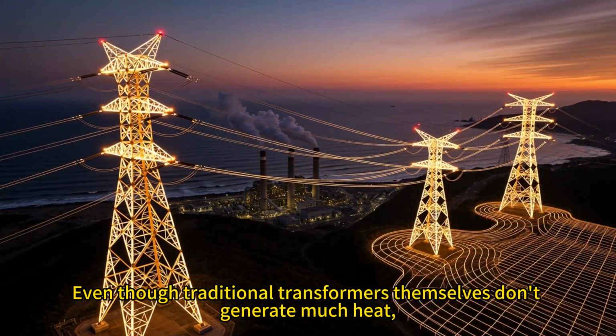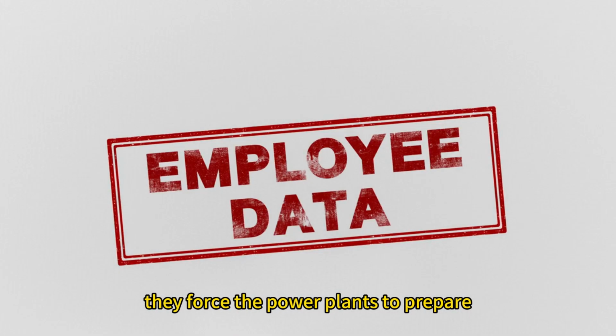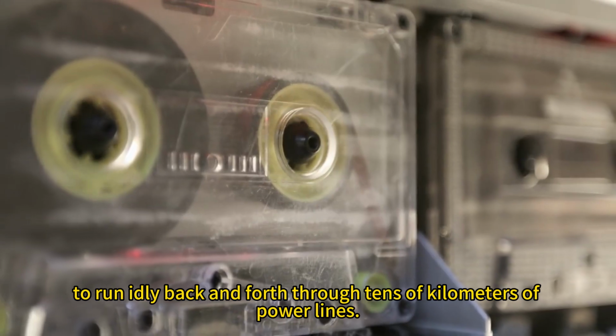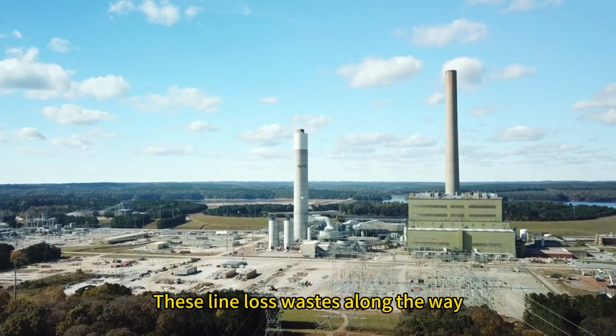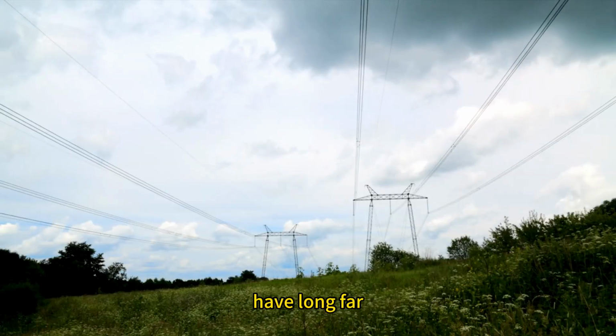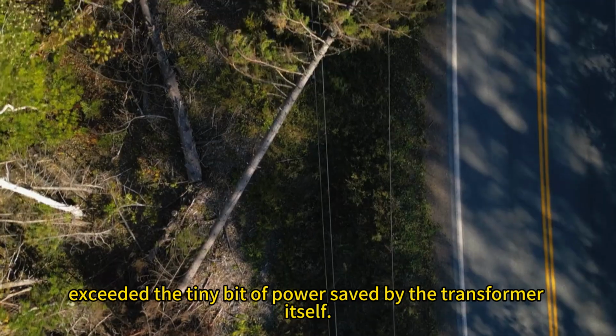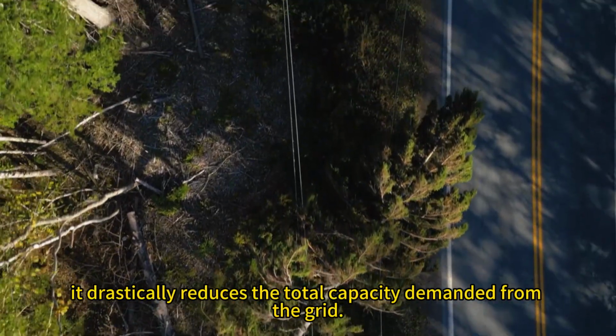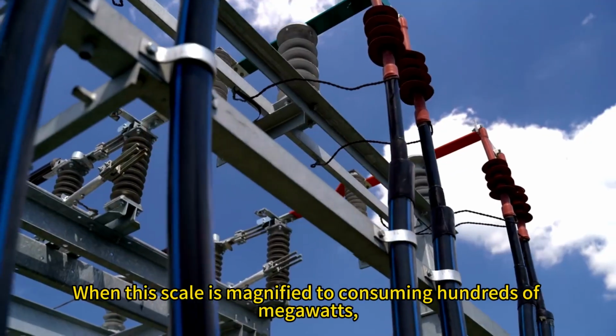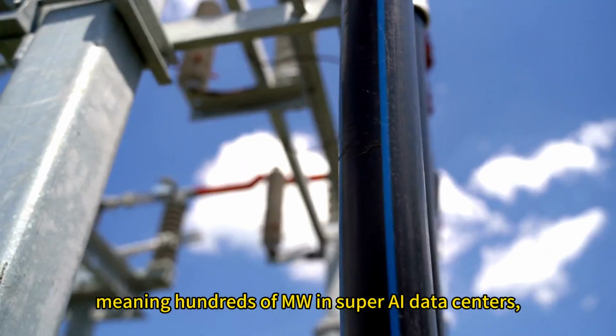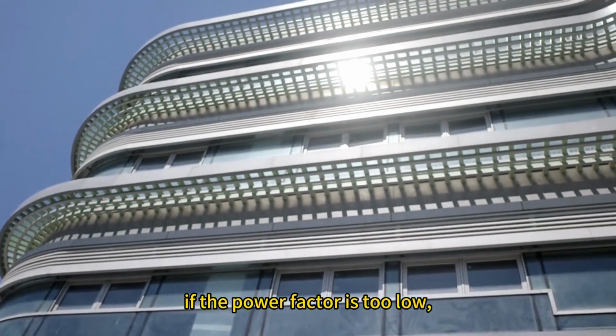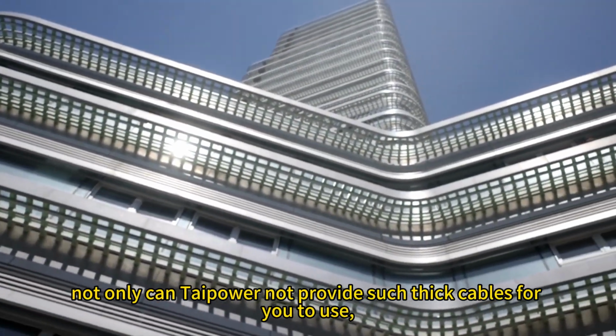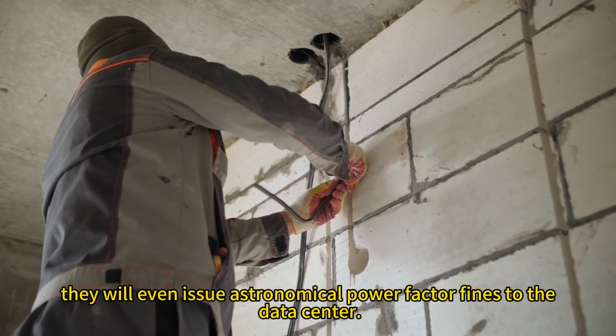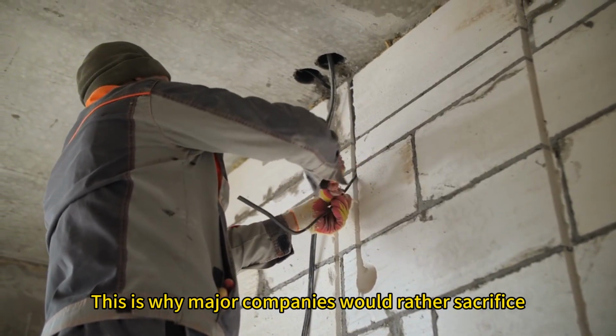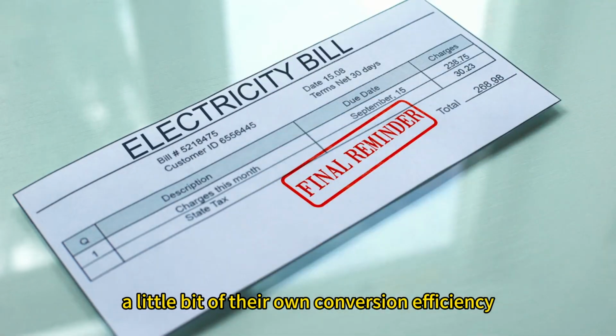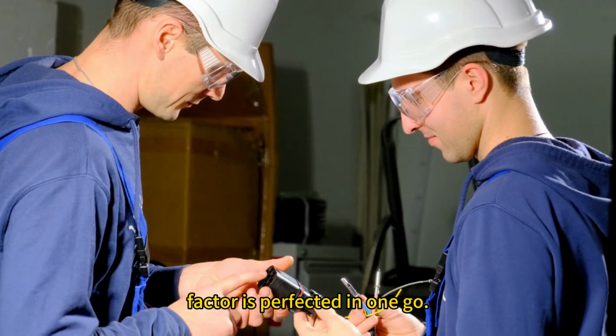Even though traditional transformers themselves don't generate much heat, they force the power plants to prepare over 200 kVA of reactive power to run idly back and forth through tens of kilometers of power lines. These line loss wastes along the way have long far exceeded the tiny bit of power saved by the transformer itself. While the SST generates a little heat itself, it drastically reduces the total capacity demanded from the grid. When this scale is magnified to hundreds of megawatts in super AI data centers, if the power factor is too low, not only can Taipower not provide such thick cables for you to use, they will even issue astronomical power factor fines to the data center. This is why major companies would rather sacrifice a little bit of their own conversion efficiency and absolutely ensure the power factor is perfected in one go.